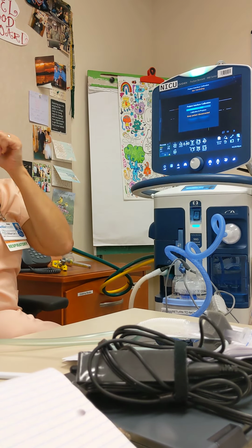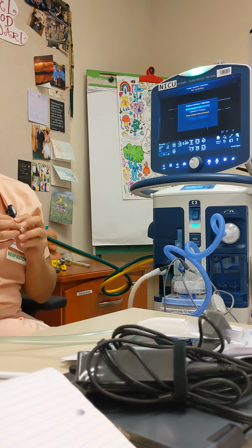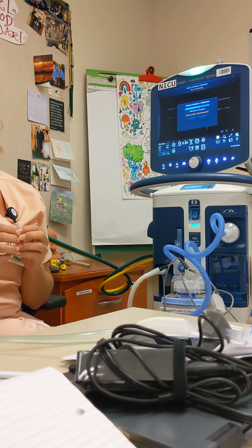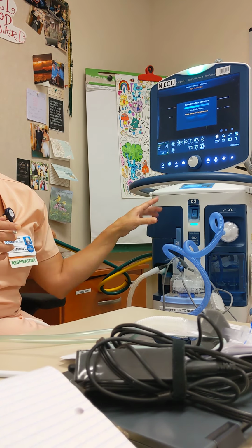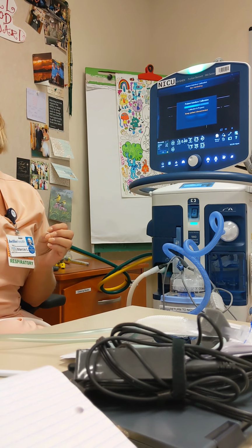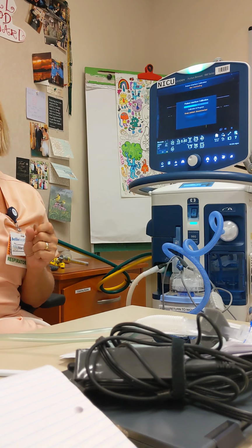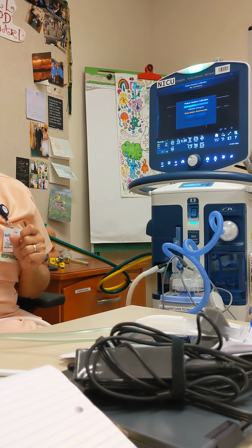It's like when we use bi-level in adults where there's that constant disconnect. Correct. But we won't have to worry about that. Potentially, besides these 3 vents, you could use that leak sync for adults too, but only on these 3. Unless we have them on bi-level, it's leaks. Is there a leak sync enable on all of them? I didn't know that. Leak sync enable. Oh, okay.